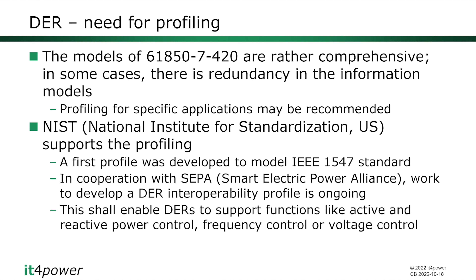We're developing a DER interoperability profile, not only for the grid codes but also for some generic applications, such as DERs that support functions like active and reactive power control, frequency control, and voltage control. We're collecting the requirements for these use cases, mapping them into the 7-420 model, and trying to build a profile out of 7-420 for those applications. This is ongoing work, supported by NIST.